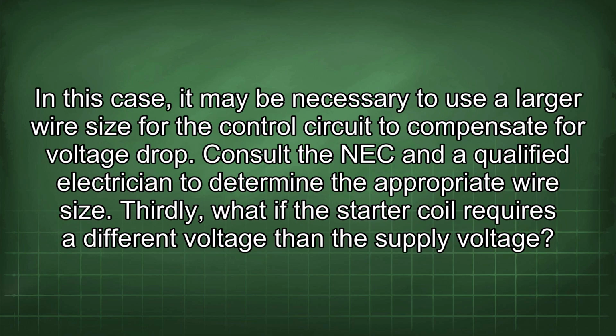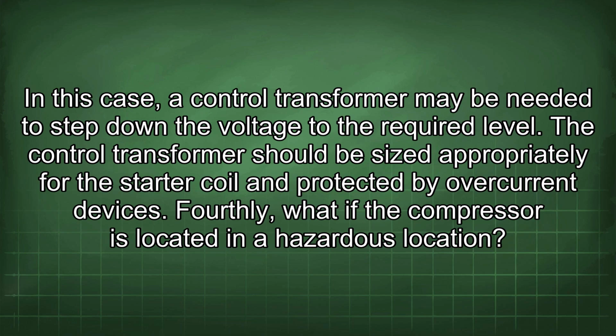In this case, it may be necessary to use a larger wire size for the control circuit to compensate for voltage drop. Consult the NEC and a qualified electrician to determine the appropriate wire size. Thirdly, what if the starter coil requires a different voltage than the supply voltage? In this case, a control transformer may be needed to step down the voltage to the required level. The control transformer should be sized appropriately for the starter coil and protected by overcurrent devices.